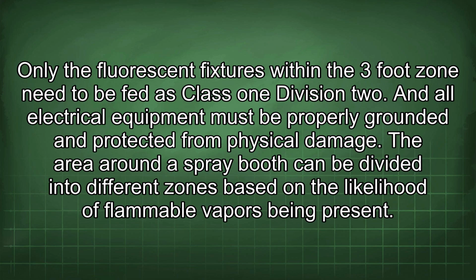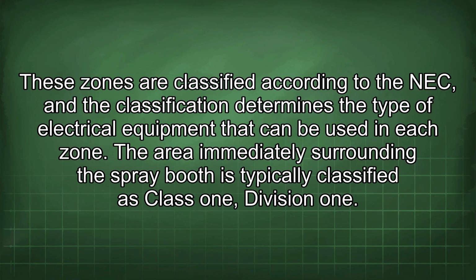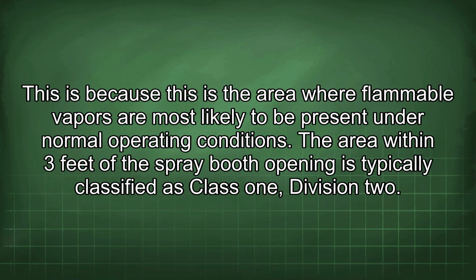The area around a spray booth can be divided into different zones based on the likelihood of flammable vapors being present. These zones are classified according to the NEC, and the classification determines the type of electrical equipment that can be used in each zone. The area immediately surrounding the spray booth is typically classified as Class 1, Division 1. This is because this is the area where flammable vapors are most likely to be present under normal operating conditions. The area within 3 feet of the spray booth opening is typically classified as Class 1, Division 2.